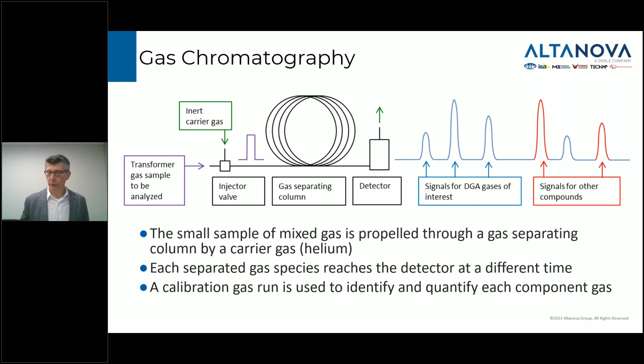And once a day, it's necessary to calibrate a GC system by injecting a known gas, a calibration gas, through the same system and measuring these peaks for that gas. So we compare our calibration gas to our actual sample at any point to make the accurate readings. Now, a lot of advantages to chromatography. It's the most sensitive technique we have. It's the most accurate one. That's why we use it in labs, and that's largely due to the automatic calibration that's done in monitors that use gas chromatography systems.